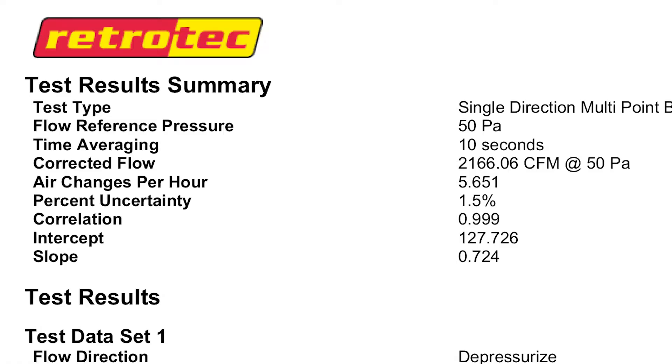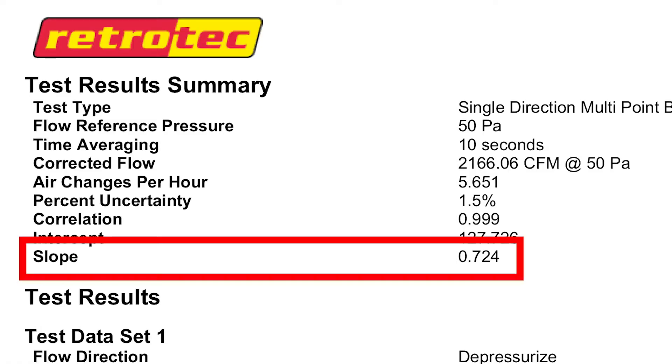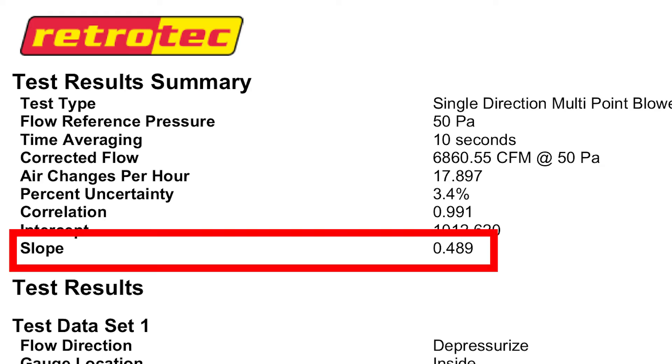As an example, I ran a blower door test on my house doing a multi-point test — just a regular test — and we can see what that pressure exponent is. But just to show you how it can reduce if you have a wide open hole, I popped a window open, did it again, and we can see that slope or pressure exponent drop down to 0.49.